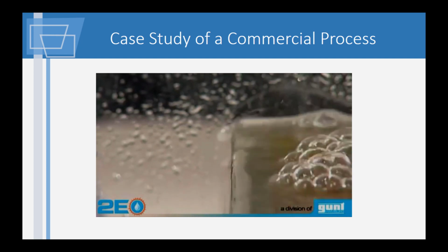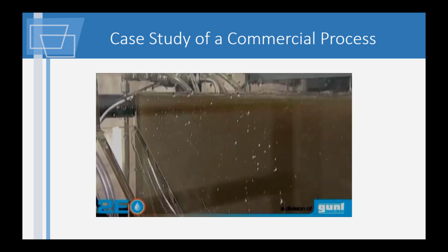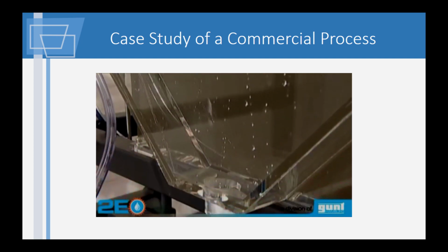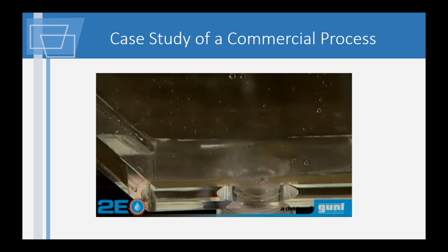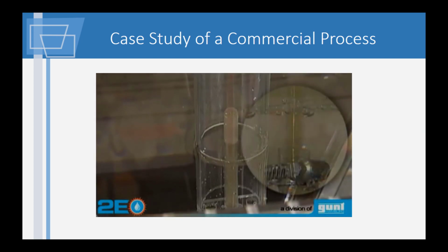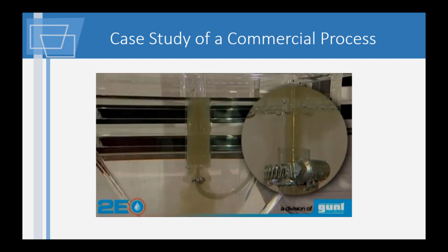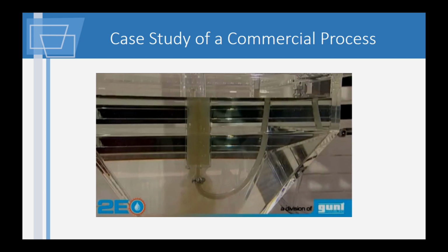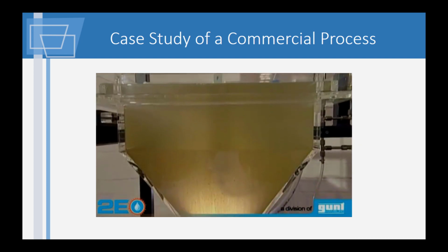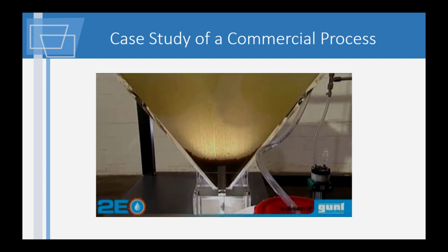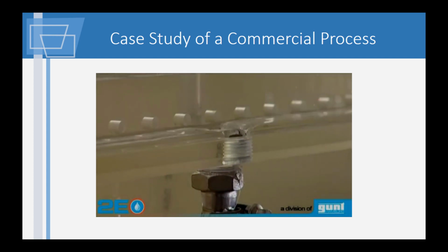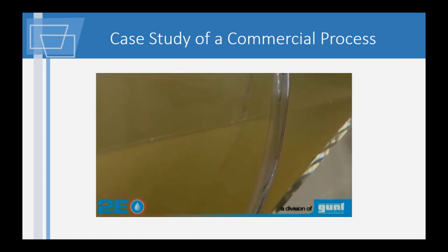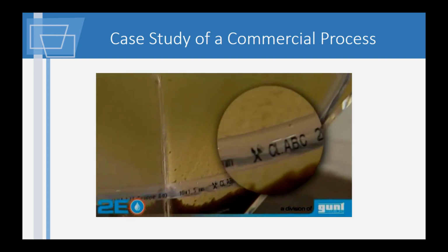As the activated sludge is suspended in the water, it is discharged continuously from the aeration tank. Therefore, the effluent of the aeration tank is fed into a secondary clarifier. The aim of secondary clarification is to separate the activated sludge from the water by means of sedimentation. While the activated sludge is returned to the aeration tank, the treated water is collected in a separate tank.